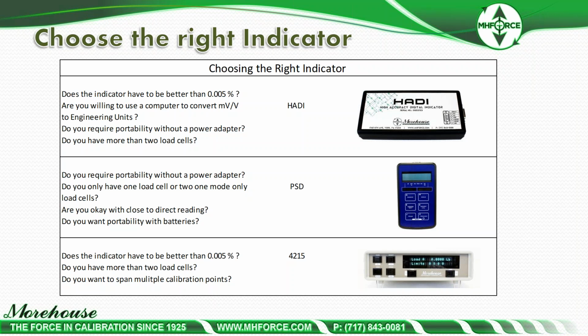If you're looking at meters, linearity is going to be something to consider. How good does the indicator need to be? You do everything right. Buy a good load cell, have it calibrated with deadweight primary standards, and then go out and look at indicators and buy the cheapest indicator. That's most likely going to be the weakest part of the system. So you really need to spec it out. This indicator right here is better than 20 parts per million. Here it says, does it need to be better than 50 parts per million? So yes, it does. This one is 20 ppm linearity. Are you willing to use a computer to convert the millivolt per volt to engineering units?